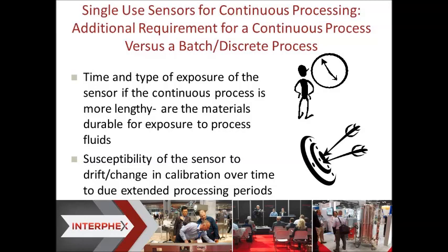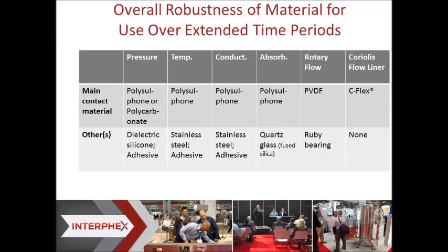In terms of continuous processing, it doesn't necessarily change the user requirements, but it adds a few more things to think about in the potential implementation. Two things are quite different when you're looking at a batch or discrete process versus a continuous process. One is the time and type of exposure. What will the sensor see over, instead of a number of hours, a number of days, 30 to 60 days? An initial cursory check would be: do the materials withstand this long-term exposure? The second thing to think about is more related to accuracy. Does the single-use sensor drift over time or change in calibration due to the extended processing conditions? We'll take a look at these two.